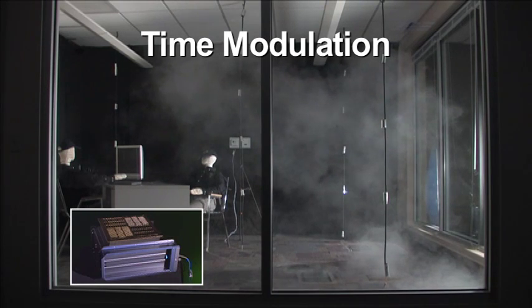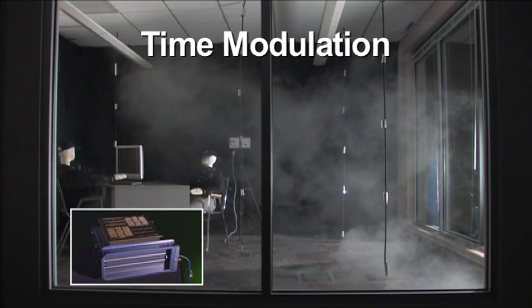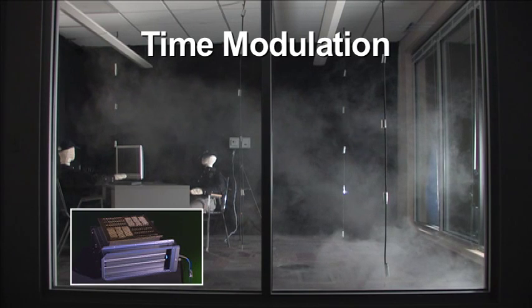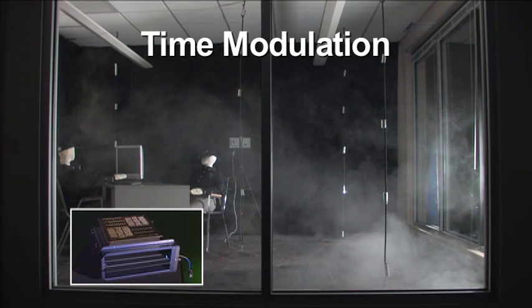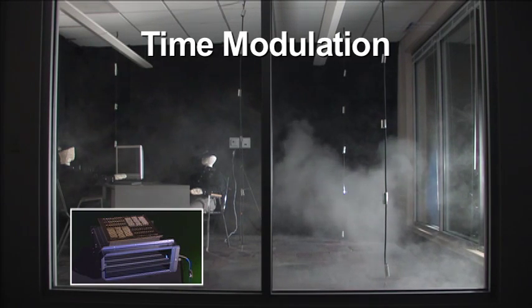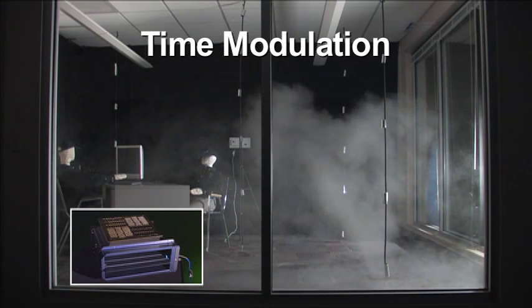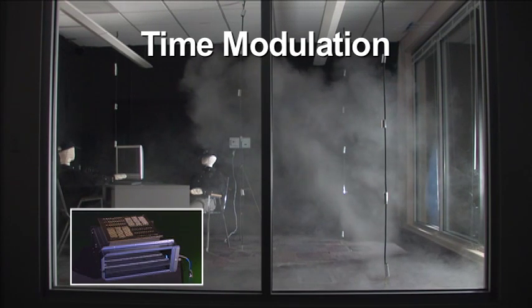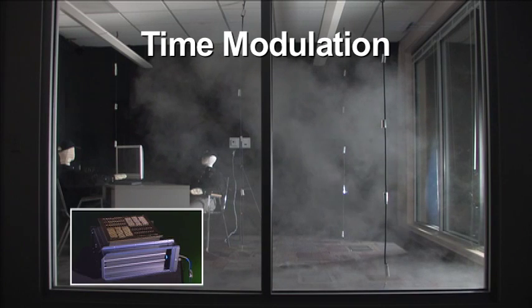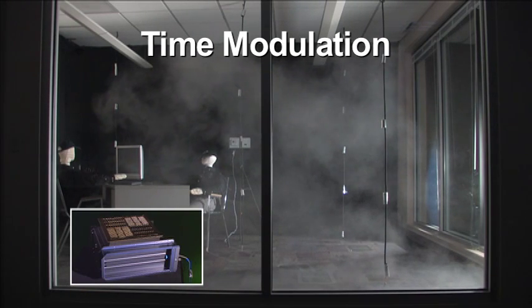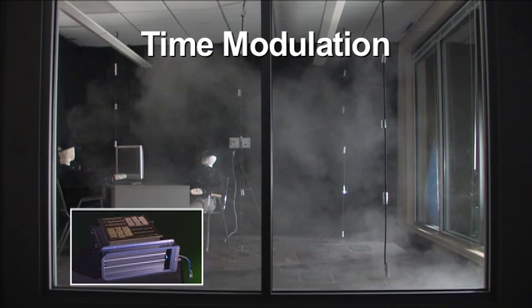The air valve is the defining difference. The diffuser is delivering the same amount of air, but you'll notice that the throw is through the entire breathing zone height and always the same throw distance. The result is much better mixing in the breathing zone and a much more consistent temperature for the occupants.